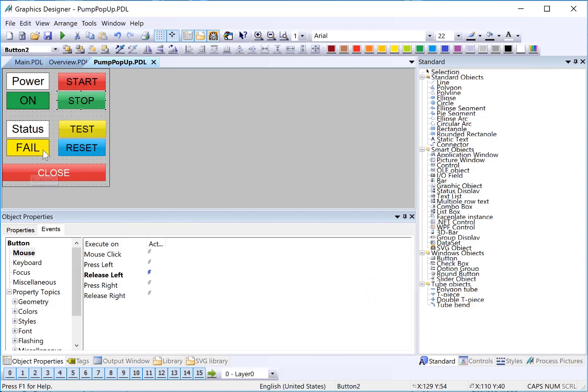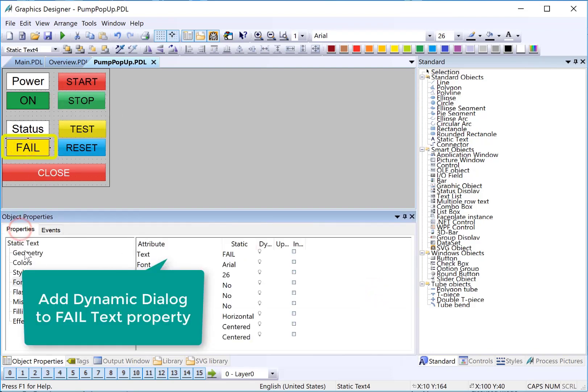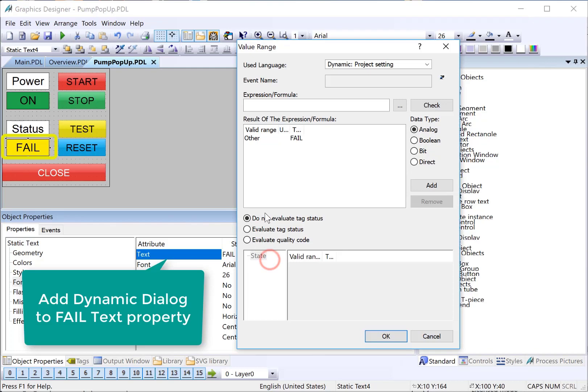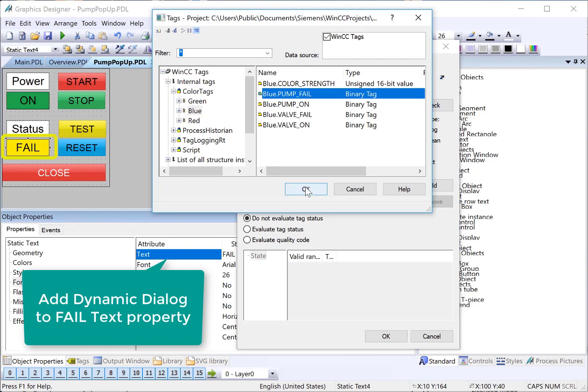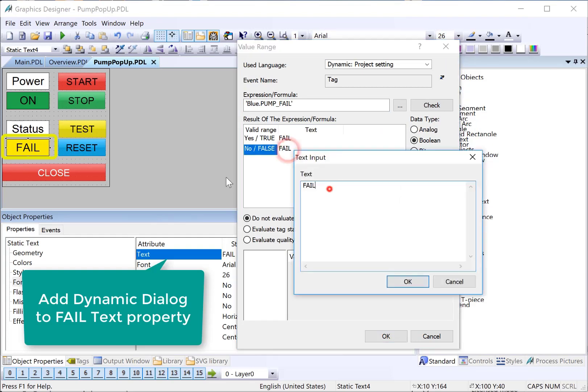We'll do the same thing down here. On our fail, make sure you go back to your properties dialog. We will go to our text attribute, do dynamic dialog. Choose our tag. This is going to be fail. And it will be Boolean. And if there's a one here, then it will say fail. If there's not a one, let's just say OK. And of course, get rid of our prefix. Make sure you leave the single quote there.